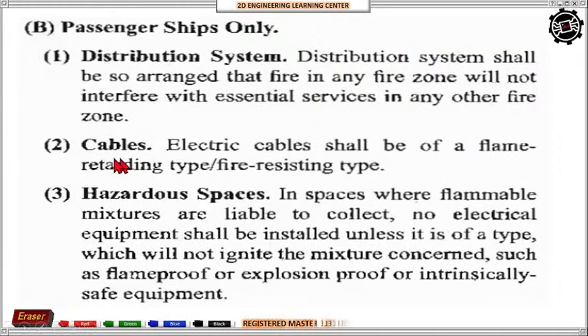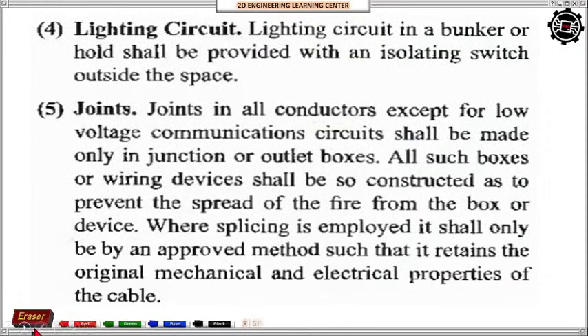Yan. So cables, electric cable shall be of flame retardant type or fire resisting type. Hazardous spaces, no, in spaces where flammable mixtures are liable to collect, no electrical equipment shall be installed unless it is of a type which will not ignite the mixture concerned, such as flame proof or explosion proof or intrinsically-safe equipment. So the lighting circuit for passenger ships, no?